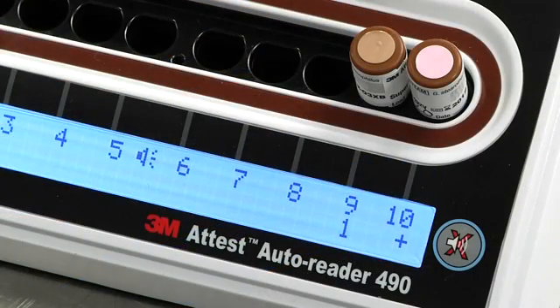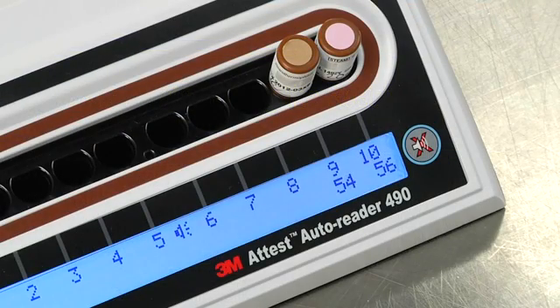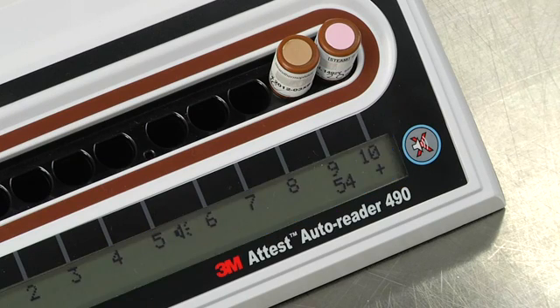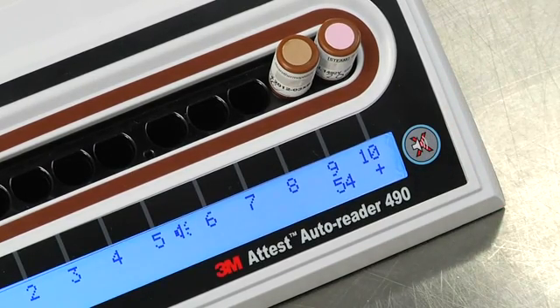Now all you need to do is wait for the result. Never remove an incubating Attest Super Rapid BI until you see a plus or minus sign on the LCD panel, which indicates the test is complete. The moment a positive result is detected, you'll see a plus sign on the LCD panel directly under the incubating BI. If the sound feature is enabled, you'll also hear an alarm, which you can silence by pushing the buzzer alarm off button. If the audible alarm is disabled and a positive result occurs, the LCD display will flash. To stop the flashing, press the alarm button.